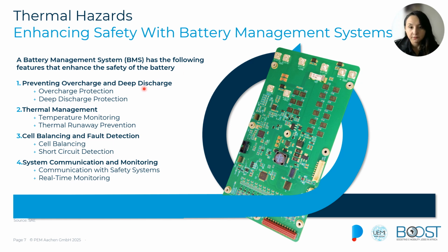Some of the features of the BMS: it prevents overcharging or over-discharging the battery by continuously measuring the voltage of all the cells in the battery. It also monitors the temperature across the battery pack, and if any of the cells begins to overheat, the system can activate cooling mechanisms or disable the battery, shutting down the system to prevent escalation of these events.